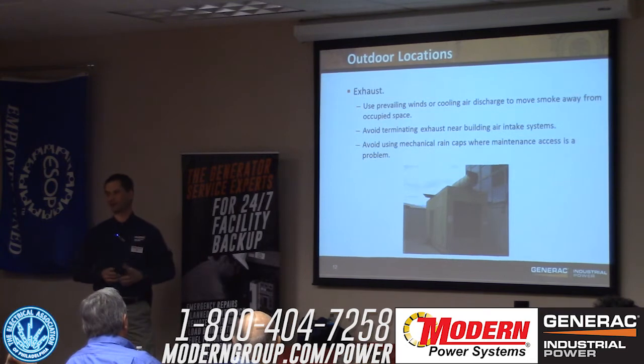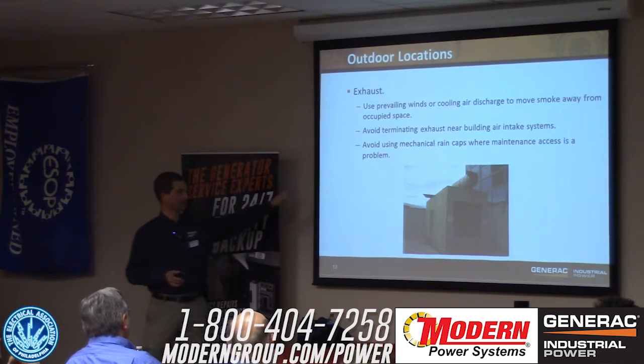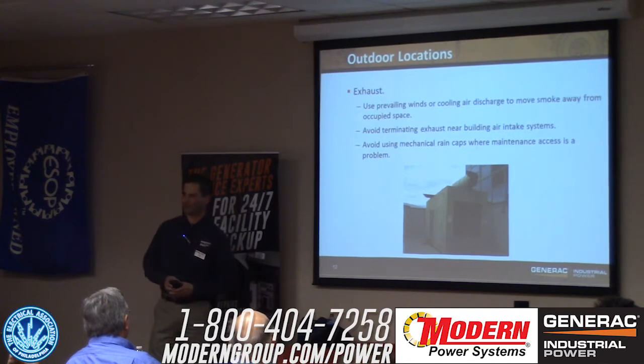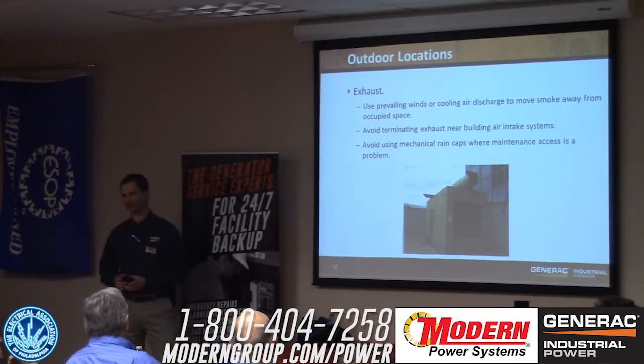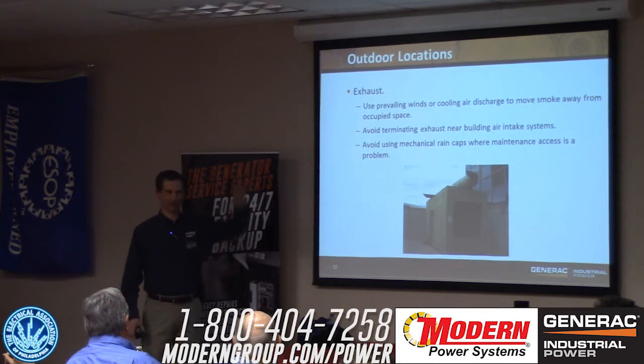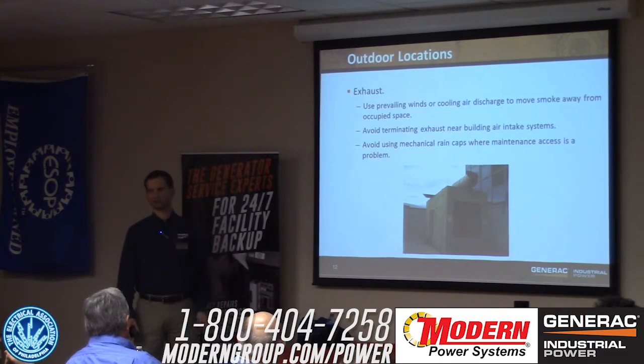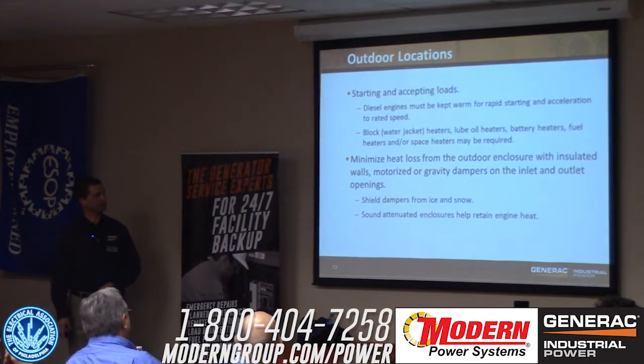Just don't terminate exhausts near an intake, or near an air intake. And oddly enough, if you can avoid mechanical rain caps, avoid them, unless you can get to them. Murphy's Law totally applies here. If you can get to and touch a mechanical rain cap, it will never ever give you a problem. In 100 years, it will never give you a problem. The moment you put it out of reach, it'll seize up or get iced over or something like that.